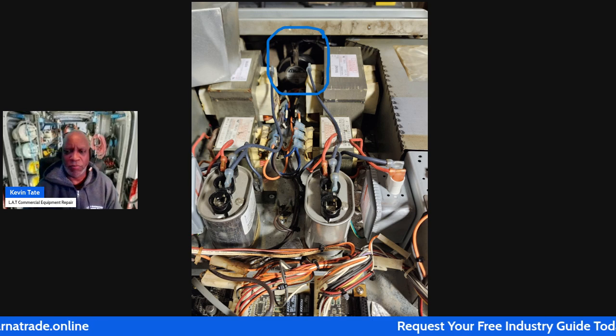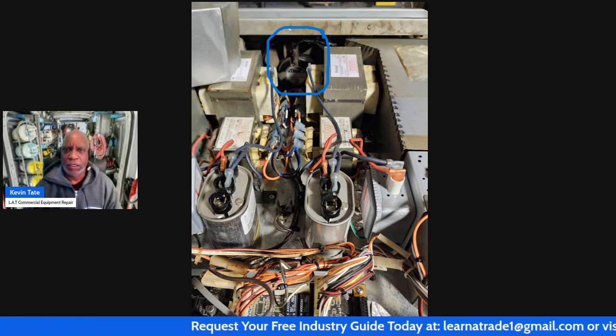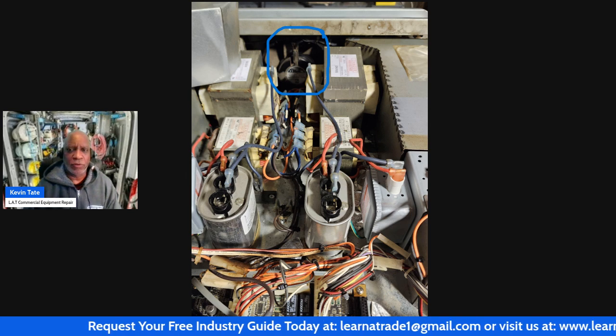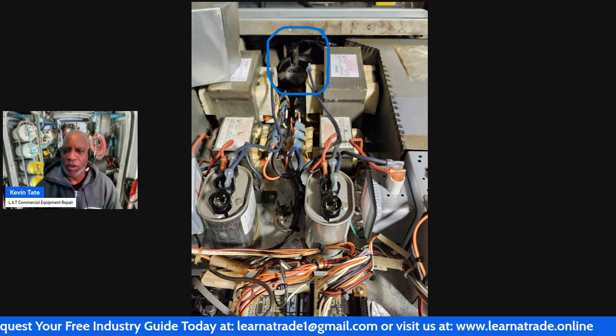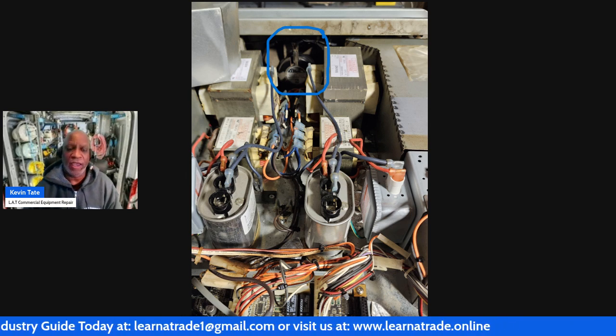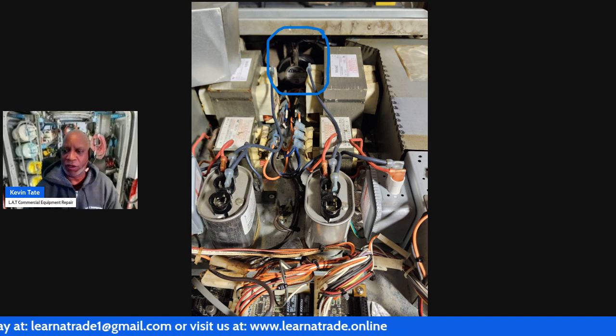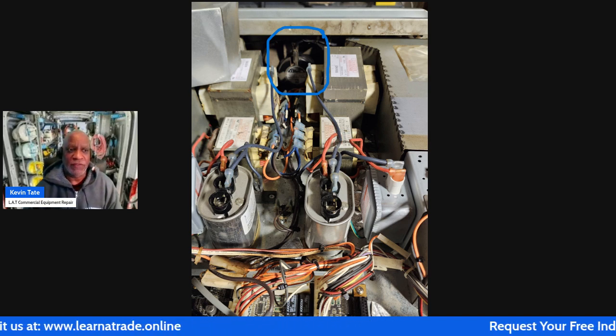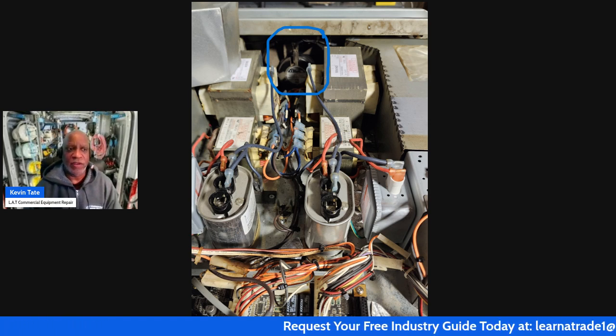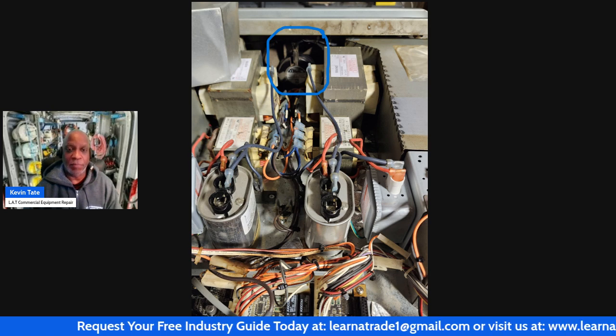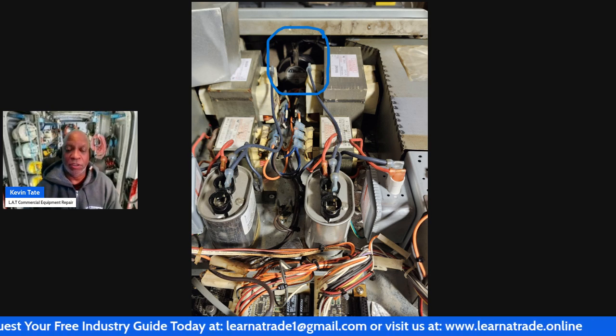around 150 to 158 degrees, if it gets to that temperature it will usually go ahead and trigger that F6 error code. The reason I circled that fan in the back is because most times that fan will not be operating properly, or not turning at all.